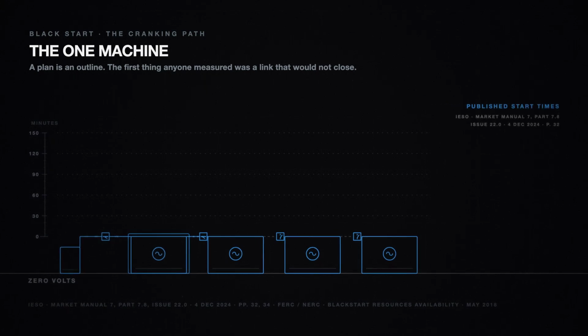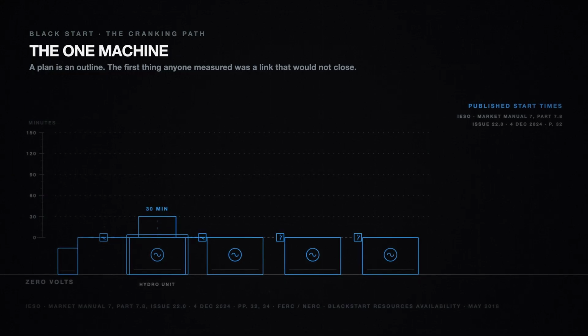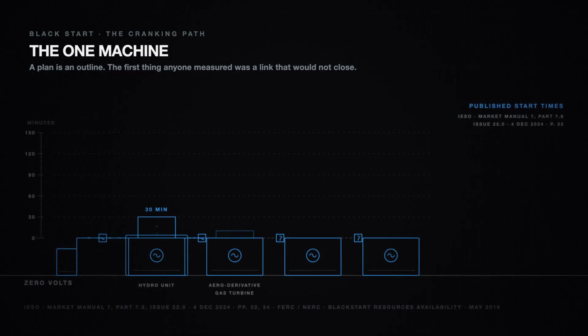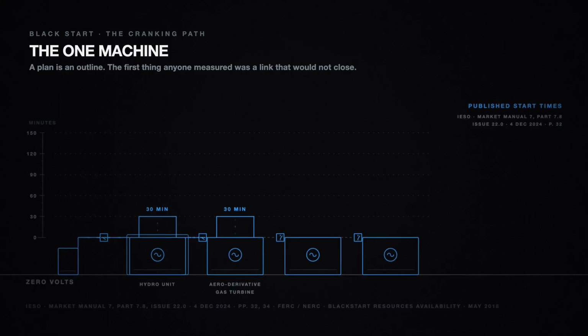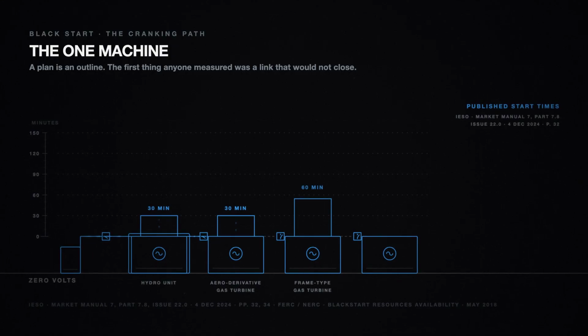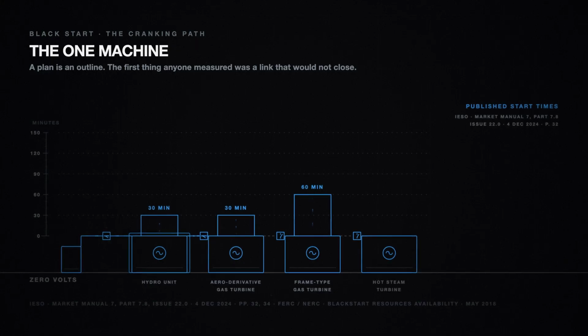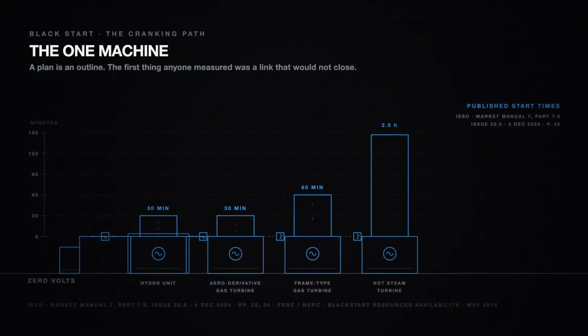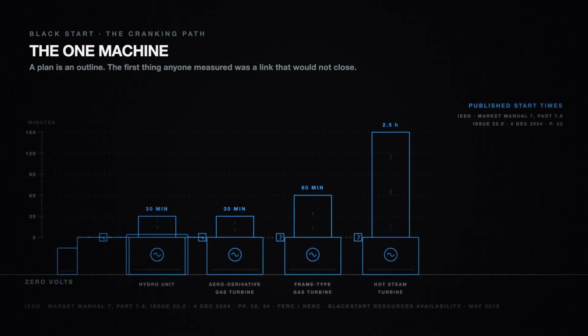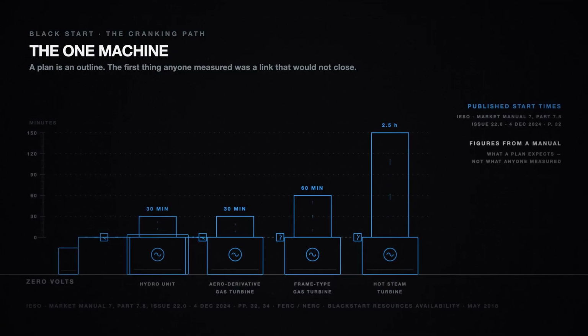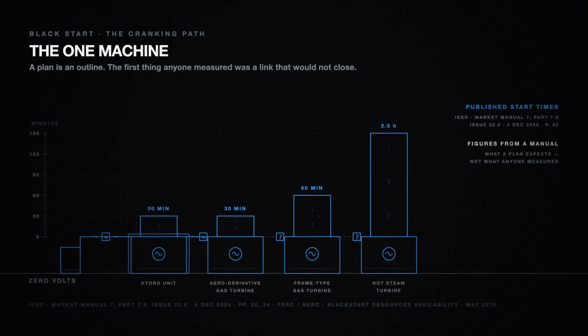Ontario's system operator publishes how long each kind is expected to take. 30 minutes for a hydro unit or an aeroderivative gas turbine, 60 for a frame-type gas turbine, 2.5 hours for a hot steam turbine. Those are figures from a manual. They are what a plan expects, not what anyone measured on a night when it mattered.